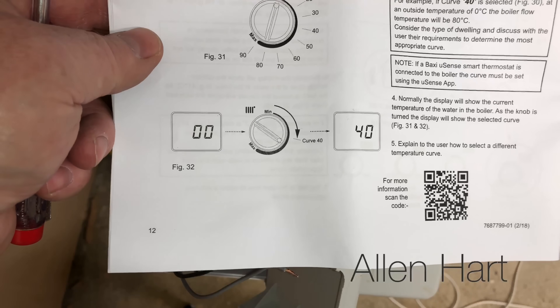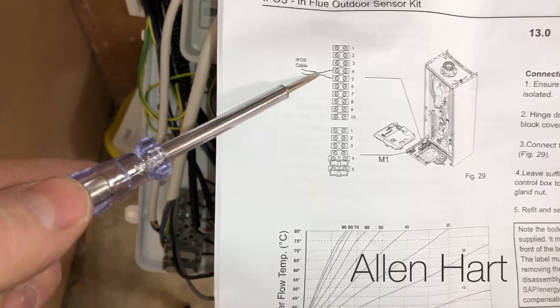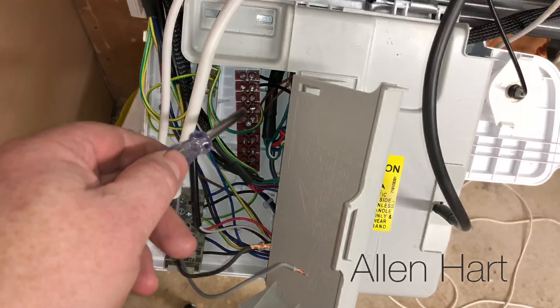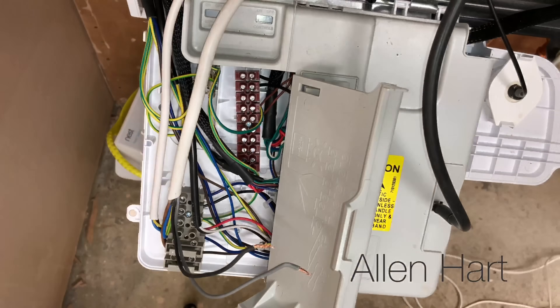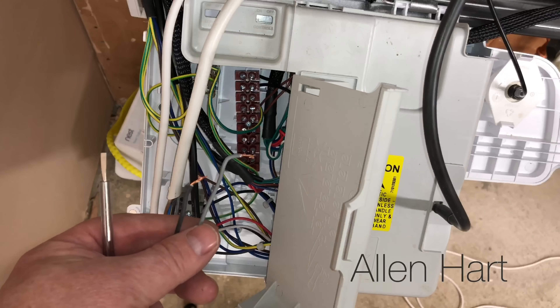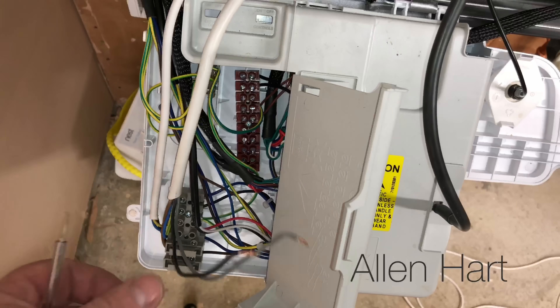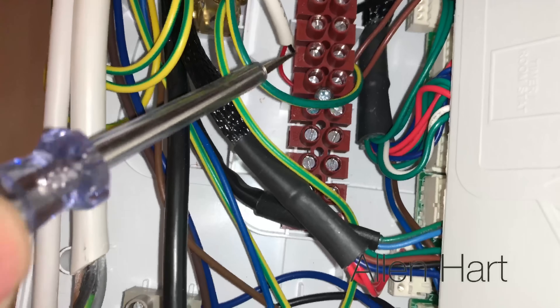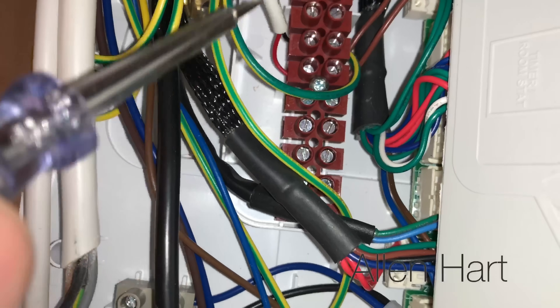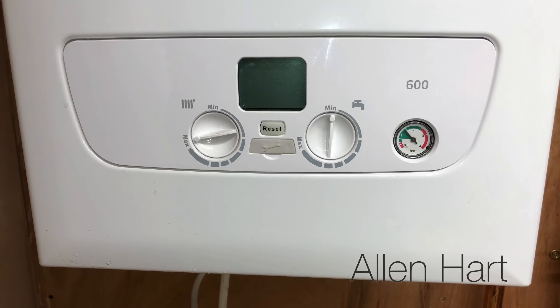For the Baxi 600 we're looking at page 12 of the instructions, and if you look on page 12 it shows you the terminals we want — number 4 and number 5, which are these brown wires here. These loose wires were for the Nest thermostat, which was wired in as OpenTherm, so I'm just disconnecting them for now. We've connected the sensor wires into where the brown wires are — that's terminals number 4 and 5.